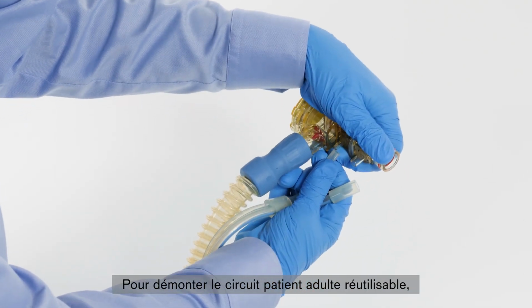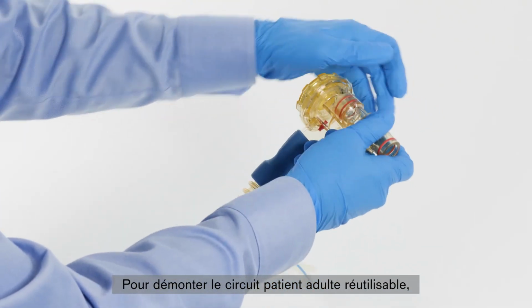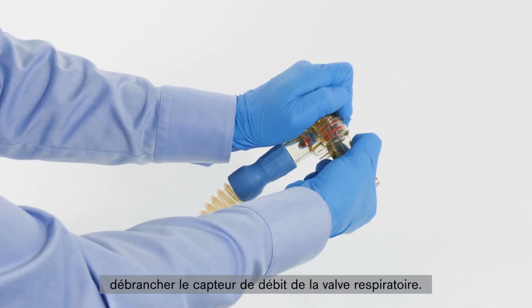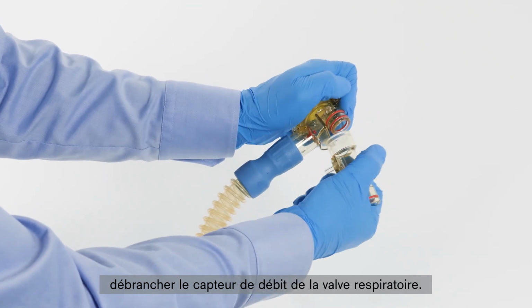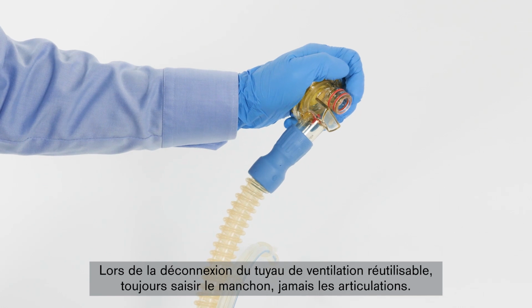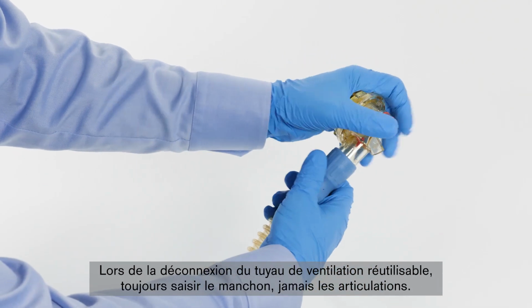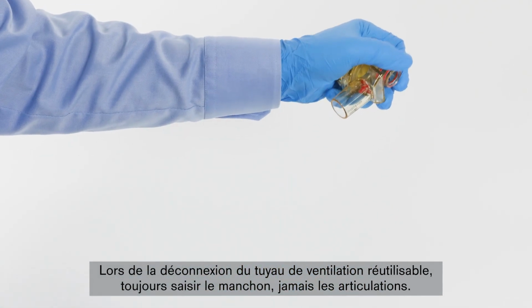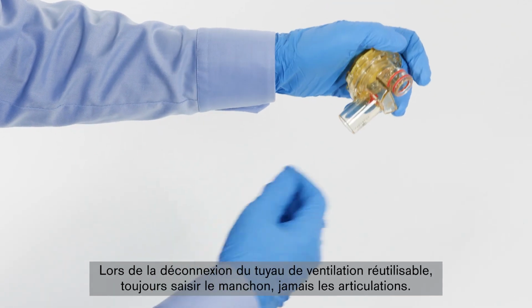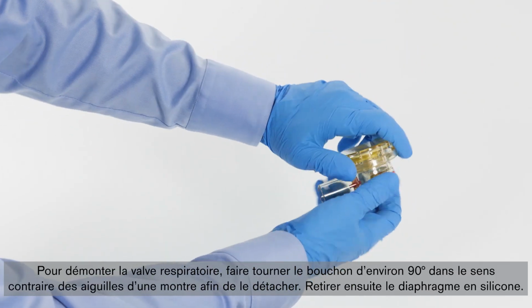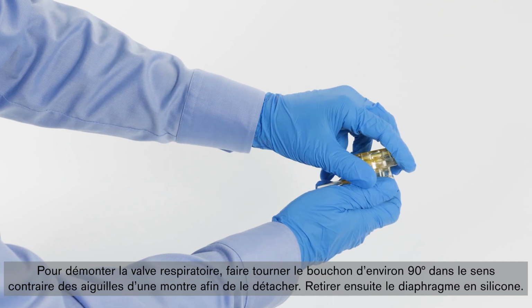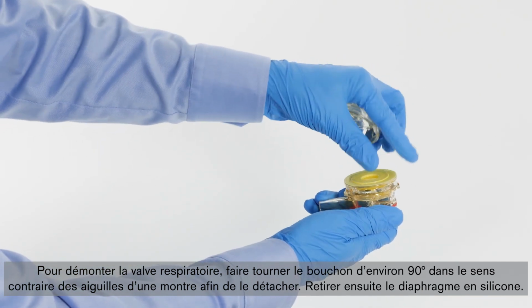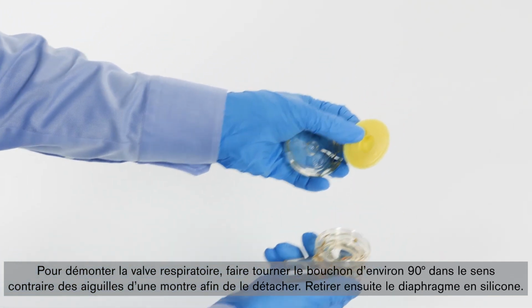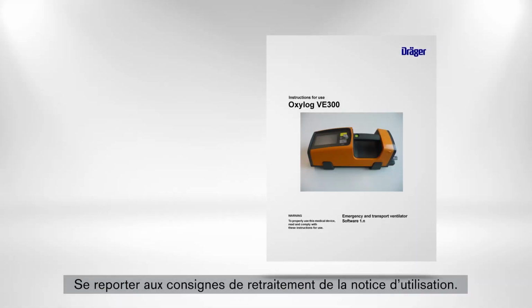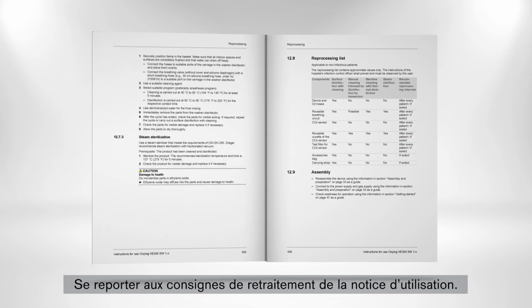To disassemble the reusable breathing circuit for adults, disconnect the flow sensor from the breathing valve. Always hold the sleeve, never the folds, when removing the reusable breathing hose from the device. To disassemble the breathing valve, turn the cap about 90 degrees counterclockwise to detach it and remove the silicone diaphragm. Refer to the reprocessing list in the instructions for use.